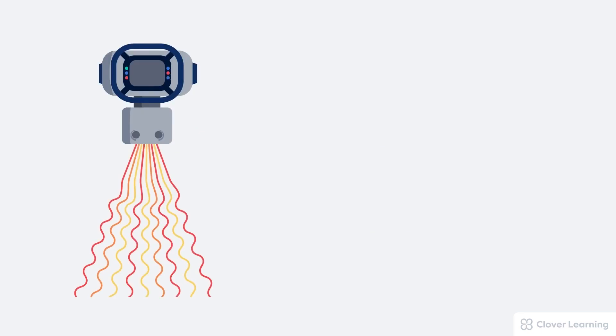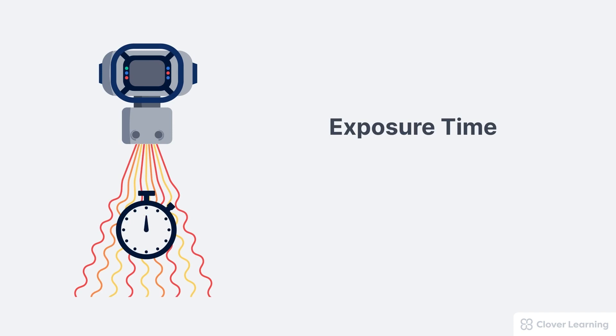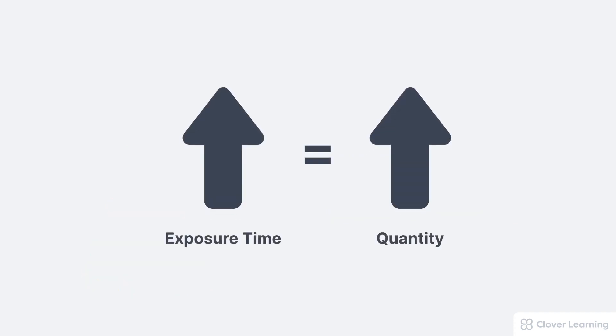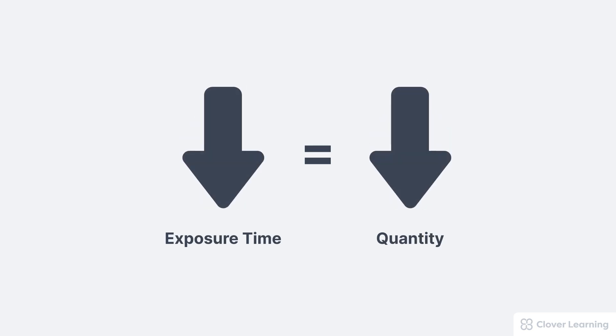Another factor affecting beam quantity or intensity is the exposure time. Exposure time simply refers to the total amount of time that electrons are flowing in the tube and x-rays are being created. The longer the tube stays on, the more total x-rays are produced. Like the mA, exposure time plays a major role in controlling the total number of photons. As we increase the exposure time, this increases the quantity or total intensity of the x-ray beam. Decreasing the exposure time results in decreased beam quantity or intensity.